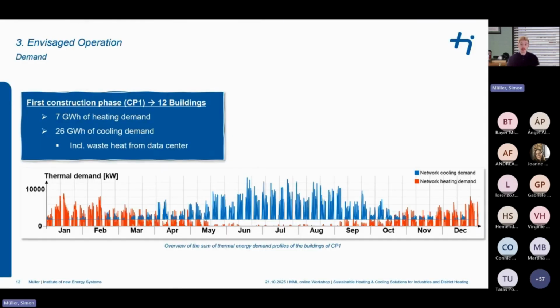Now we'll look closer at the envisaged operation of buildings and networks in construction phase 1. There are 12 buildings planned, including office buildings, a security center where security features of cars are tested, and a data center with significant waste heat potential. The demands of all buildings in construction phase 1 sum up to around 7 gigawatt hours of heat demand per year and around 26 gigawatt hours of cooling demand.